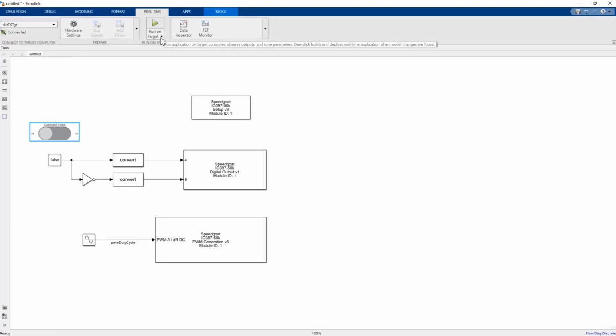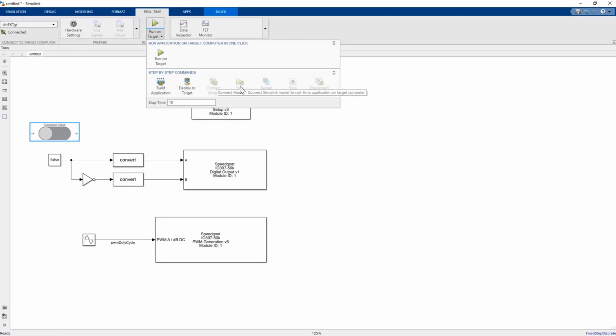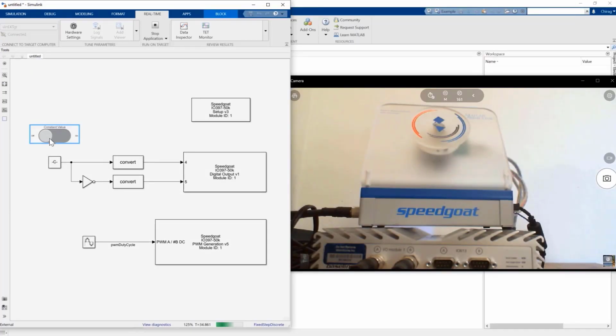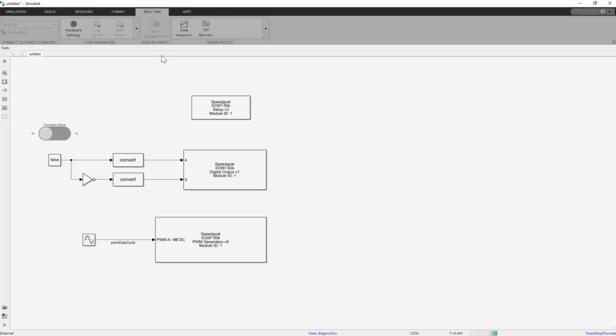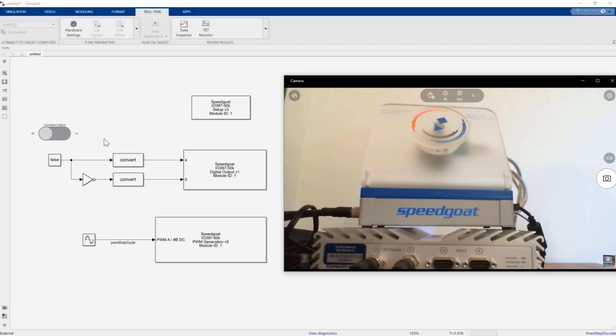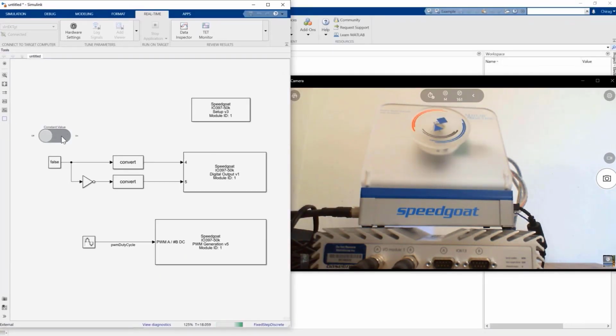We can now connect, deploy, and run the controller to the target, and the motor will start spinning. We're first just spinning the motor with scalar control, providing three-phase sinusoidal voltages whose amplitude and frequency create a rotating magnetic field that starts rotation of the permanent magnets in the rotor.